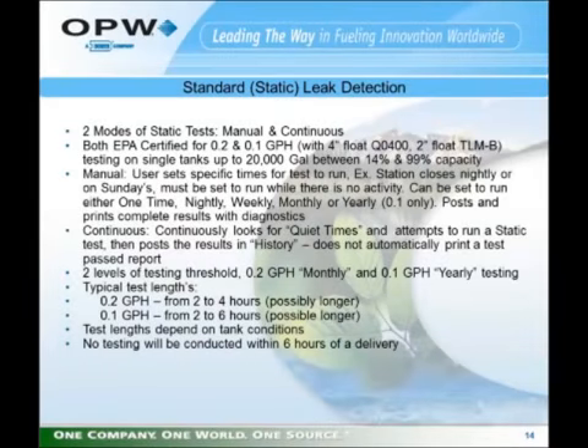When a unit is performing a standard or a static leak test, there are 2 methods of programming. One method is manual, one method is continuous. Continuous static leak detection is not to be confused with segmented leak detection. What it means is when a tank is programmed for a manual test, you are telling the unit at what date, day, time to perform the test on that tank. Now that tank must be inactive during the entire period of the test.